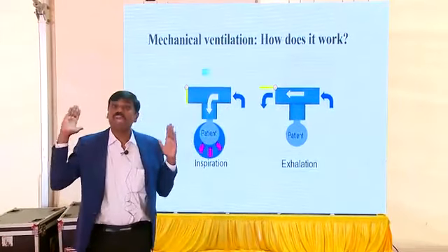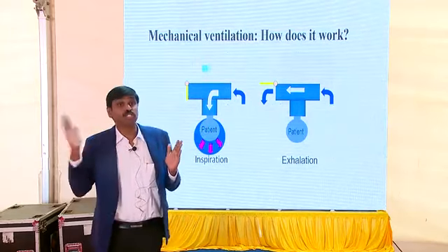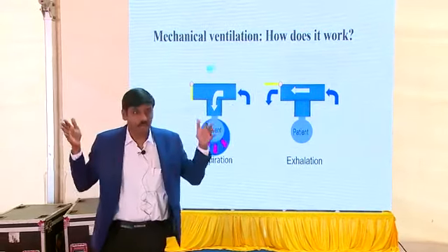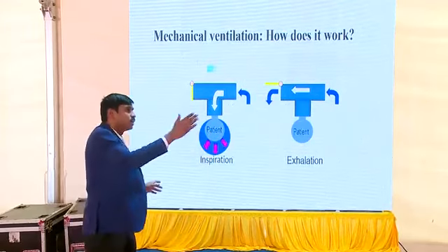Ventilator is quite simple. So the expiratory valve controls how long the expiration is going to be, and depending on how much it's open or closed, you can also control the gas flow. So that's a simplified part of ventilation. Okay, next one.